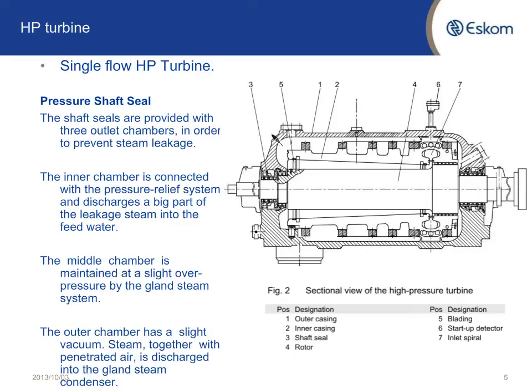The shaft seals are provided with three outlet chambers in order to prevent steam leakage. The inner chamber is connected with the pressure relief system and discharges a large part of the leakage steam into the feed water. The middle chamber is maintained at a slight overpressure by the gland steam system, and the outer chamber is at a slight vacuum. Steam together with penetrated air is discharged into the gland steam condenser. In my modelling of the glands, I didn't include the air that's going to come into the steam.